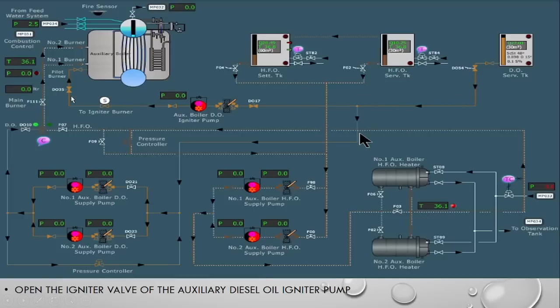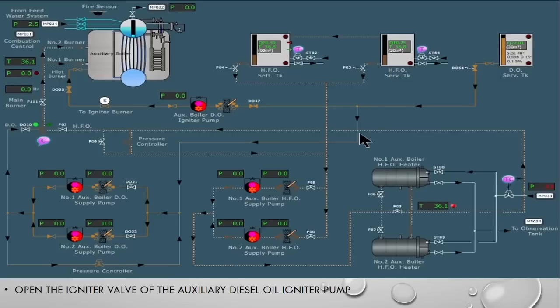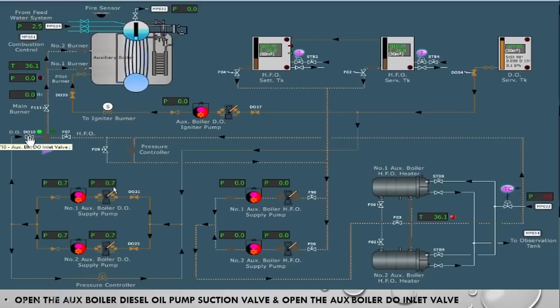The second thing we do: since we are firing the boiler in DO, we must make sure the suction and discharge valves of the DO pump are open. We open the suction and discharge valves of the DO supply pump. After opening those, we open valve DO10. Now what is happening: oil is coming from the DO service tank — one line goes to the DO igniter pump, and another is made available to the DO supply pump.